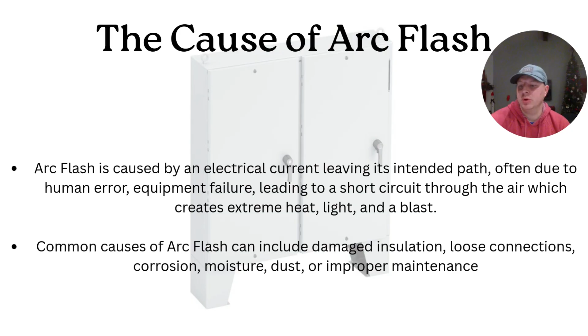If you open your codebook, NEC Article 110.16, Arc Flash Hazard Warning. Under that category, A is general: electrical equipment such as switchboards, switchgear, panelboards, industrial control panels, meter socket enclosures, and motor control centers that are in other than dwelling units and are likely to require examination, adjustment, servicing, or maintenance while energized shall be field or factory marked to warn qualified persons of potential electrical arc flash hazards.